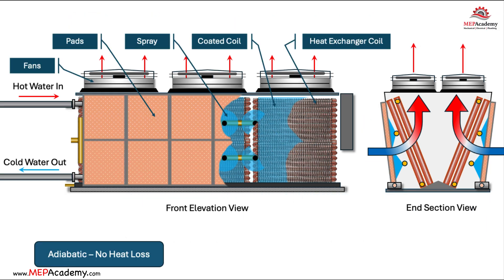Adiabatic fluid coolers or condensers operate like dry cooling systems, except they have water running over pre-cooling pads. As air is drawn through the pads, the ambient dry bulb temperature of the incoming air is depressed. This reduced dry bulb temperature provides for greater system heat rejection than any dry system.